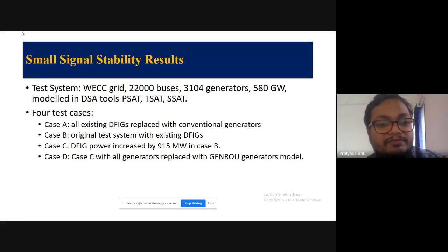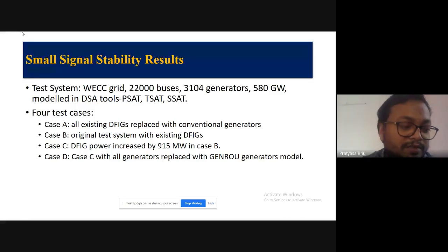Case C is where the DFIG power is increased by 915 megawatts over case B. It was forecasted that wind generation will be increased by 915 megawatts, so in case C we increase the renewable DFIG power generation by 915 megawatts. In case D, all the renewable generators in case C are replaced with GENROU synchronous generators. So in cases B and C we have DFIG or renewable generation. In cases A and D we have all conventional generators.